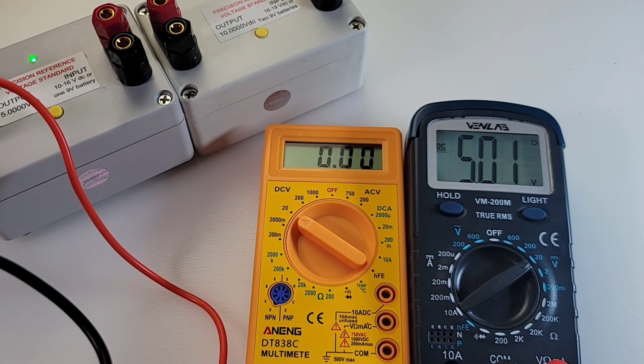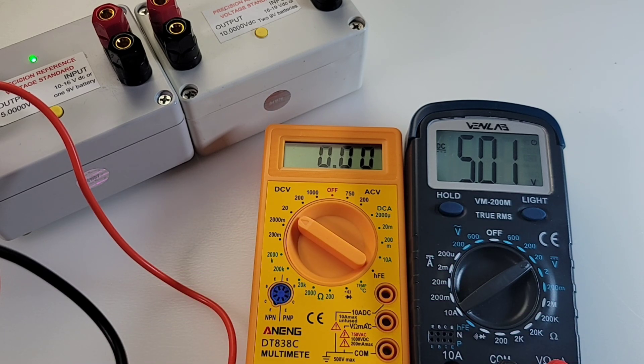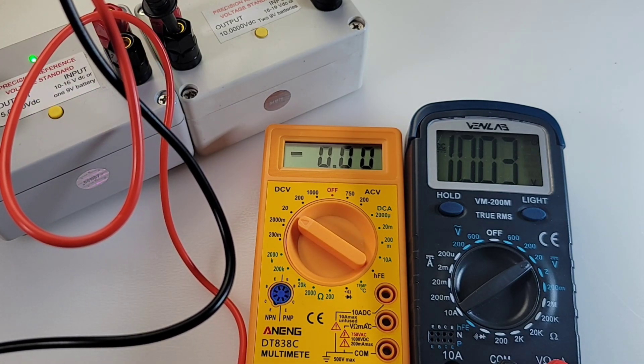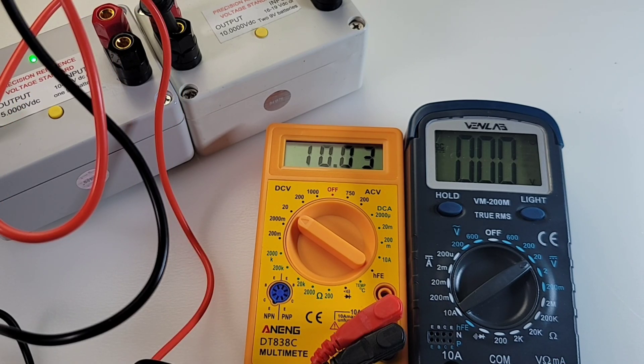Starting off with the DC voltage test. I've got these precision voltage references from Fred Chu — he's sending me some new goodies for 2023. If you're looking for a voltage or current reference, check out his eBay link included in this video — he's got some great gear. Sitting at 5.01 volts — want to see 5.0, so not bad. Let's try the 10-volt reference — should see 10.00, coming up as 10.03. It's in spec. The Aneng also reads 10.03.